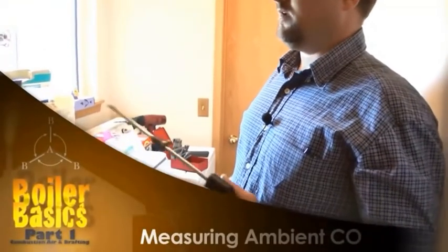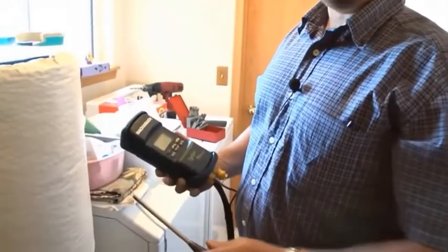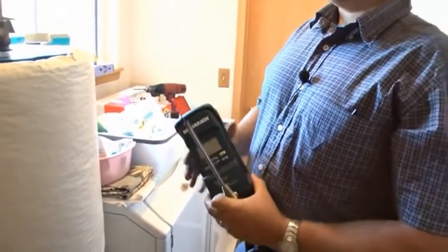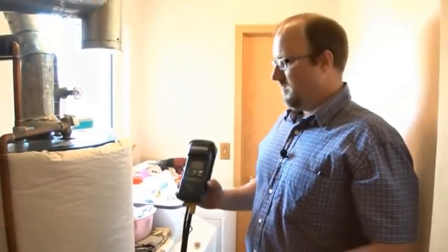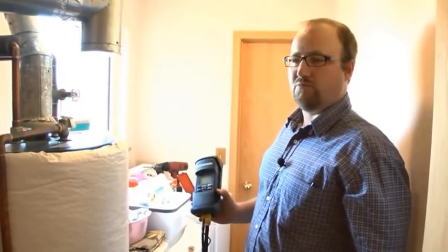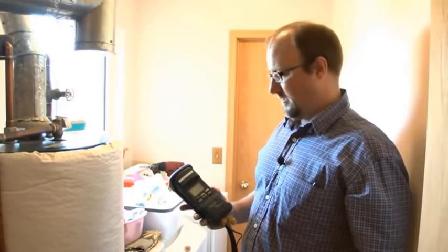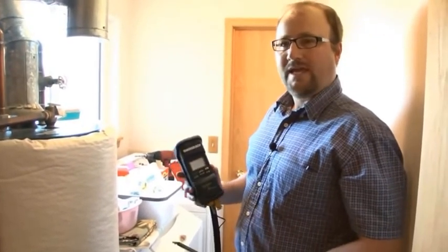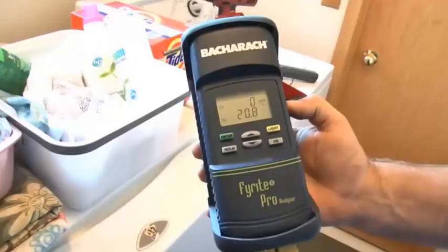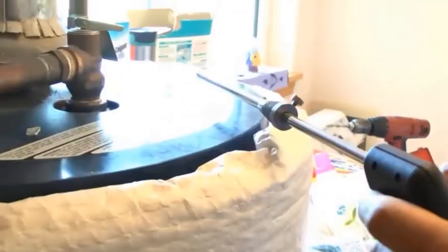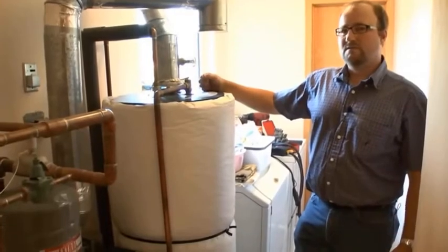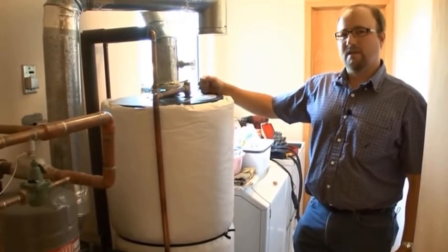While we're doing the combustion air zone testing, we want to make sure that we're not exposed to over 35 parts per million of CO ourselves. This unit's backdrafting. If it doesn't have a good burn, it's going to be kicking out some CO, and we would be breathing that CO, which is a deadly gas. So we want to be monitoring the CO in our ambient air where we're working, and make sure it's always below 35 parts per million. So we failed worst case combustion air zone under winter time conditions.